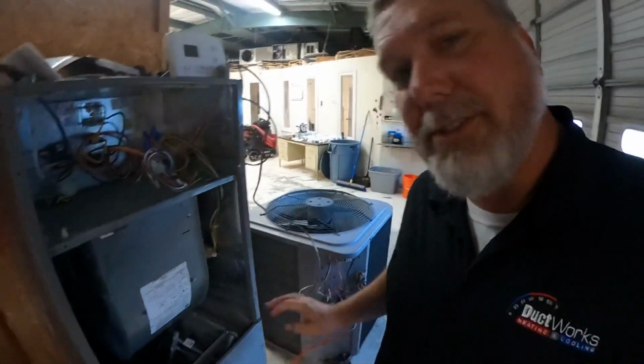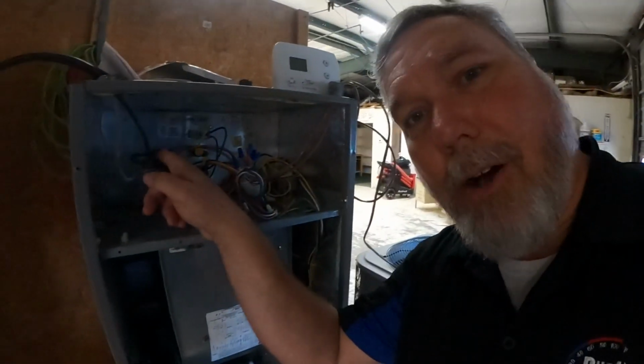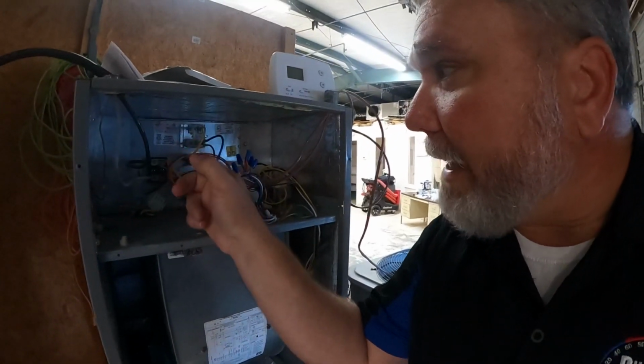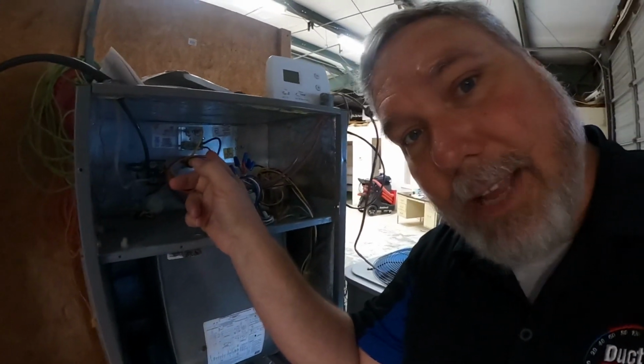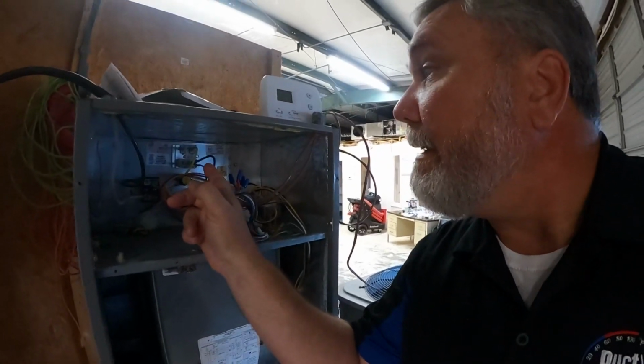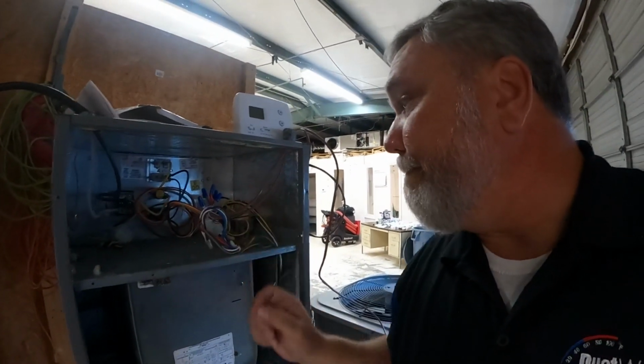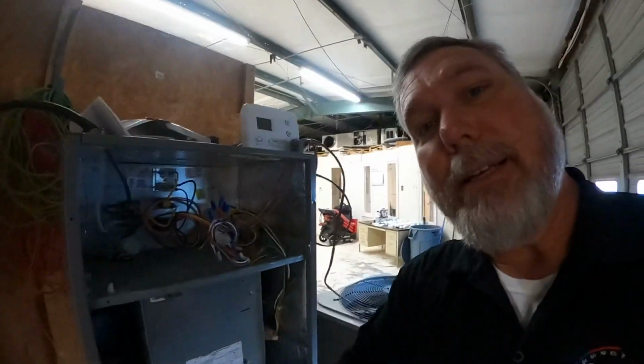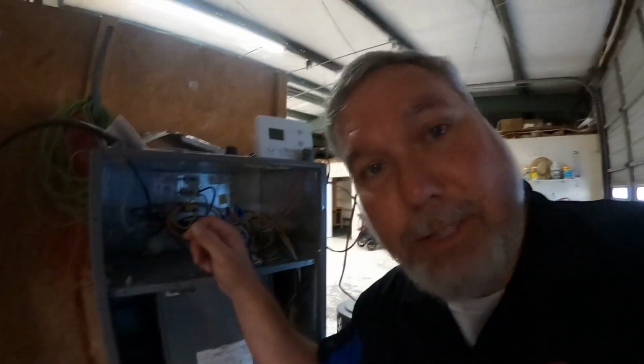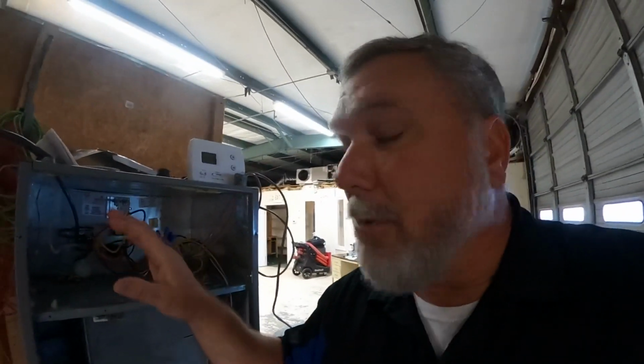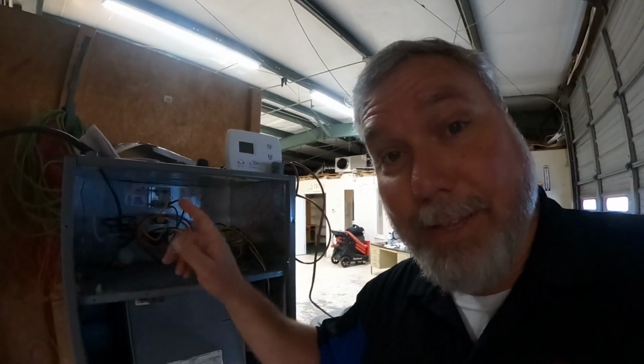Other things that we check, this is the actual air handler that's matched to this outdoor unit. We check all the high voltage controls. We check the heaters in the system. There are safety switches in there that we have to check, limit switches, and we make sure all the components are tight: the transformer, the lugs, where everything's lugged into the system. Because in the wintertime this draws more power because you have these heaters. And if you don't have everything good and tight and snug, it can lead to wires overheating and it could cause some major problems.